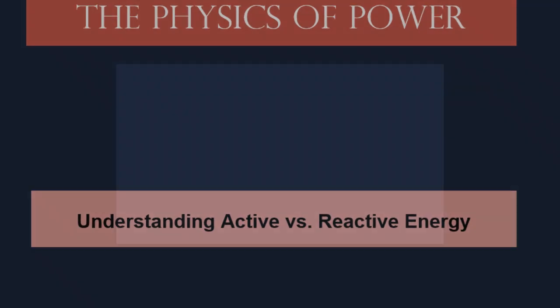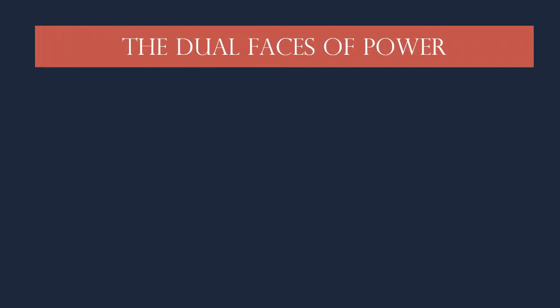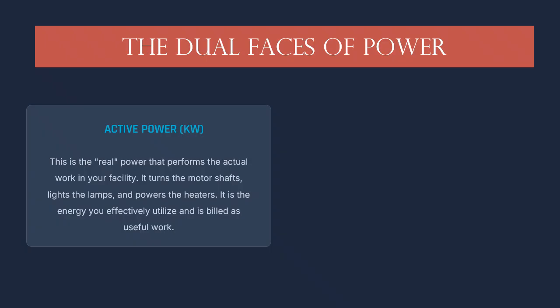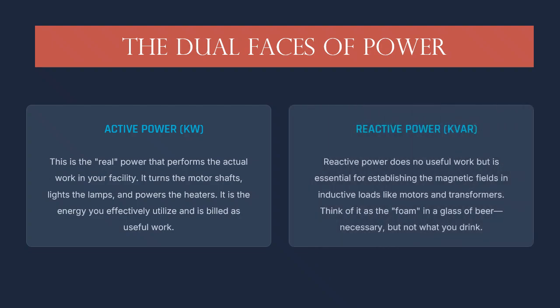The dual faces of power. Think of electrical power as having two distinct faces. On the left, we have active power, measured in kilowatts. This is the real muscle, the energy that actually turns your motor shafts and lights your facility. On the right, we have reactive power, or kVAR. While it doesn't do useful work, it is absolutely essential. It creates the magnetic fields that allow motors and transformers to function. You need both, but you only want to pay for the first.